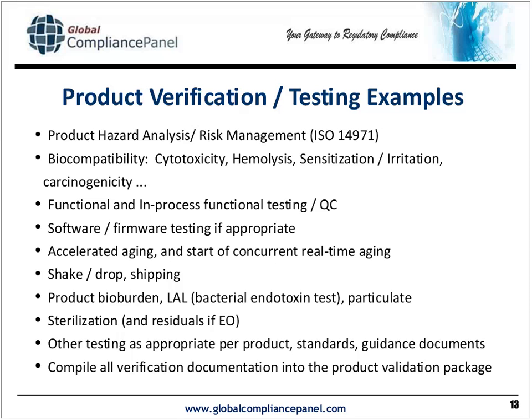And again, I follow the model, the 11-element model that the FDA has published under its document of 510K submissions containing software. I use it for all software validation. And those 11 elements are a software validation documentation package within the overall product validation package.